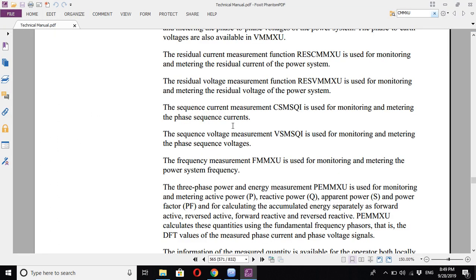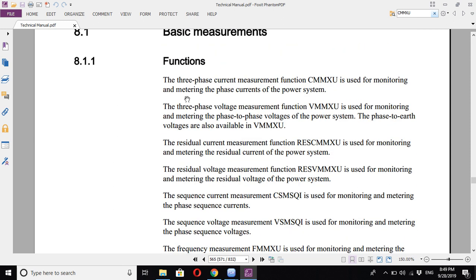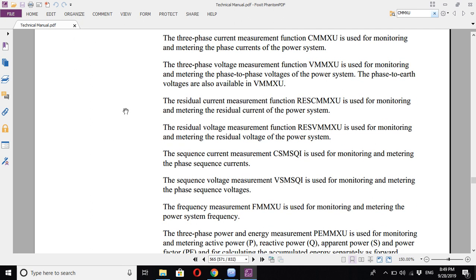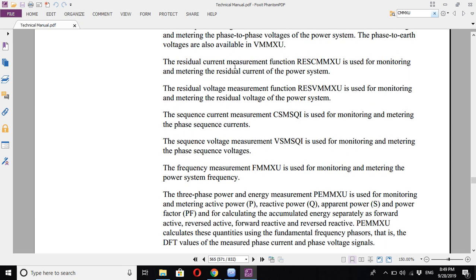According to the relay manual, you have the function blocks used for measurements such as CMMXU, which is used for monitoring and metering the three-phase currents, VMMXU used for monitoring the three-phase voltages, the residual current, and the residual voltage.